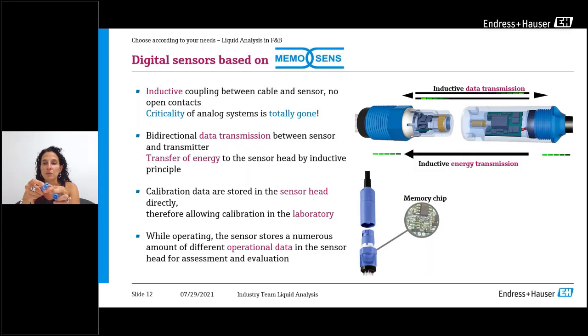How it does that, if you see in the image, you have here a coil. This coil is this one in the sensor, and this coil is inducing a current that transmits the information to the cable. And then I have on the side of the cable another coil that is this small one, that is also inducing a current for the sensor to have enough energy to work. But if you see, on none of the sides do you have any metal contact, and that is what is for the water or humid environment, or whenever you clean with water directly, the sensor has no problem because it has no metal connections. And if you have any problem in the connection between the sensor and the cable, what you will receive is just a signal that says the sensor is not connected, but you won't receive any value.